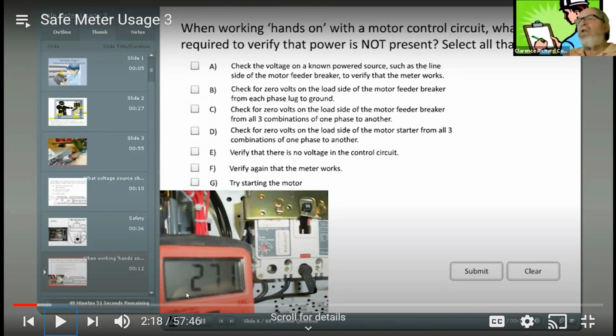Okay, A. Well, what we want to do here is we're going to get our hands in there. We're going to be on the load side of that circuit breaker doing some work. We don't want no voltage in there. We don't want no surprises. So A, check the voltage in a known power source, such as a line side of a motor feeder breaker to verify that the meter works. Is that a good idea?